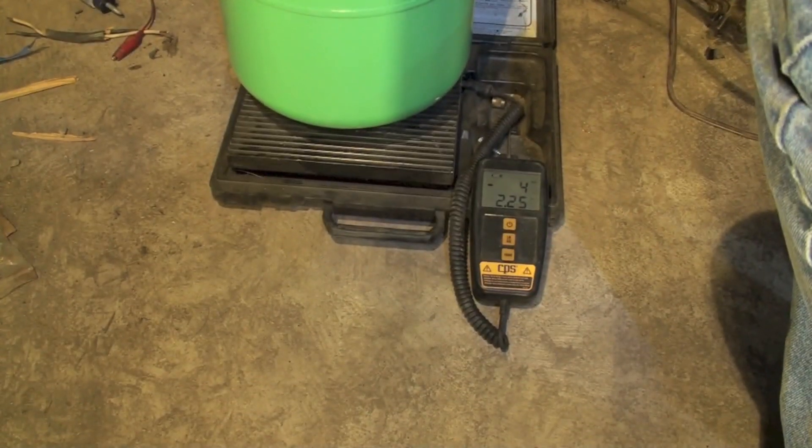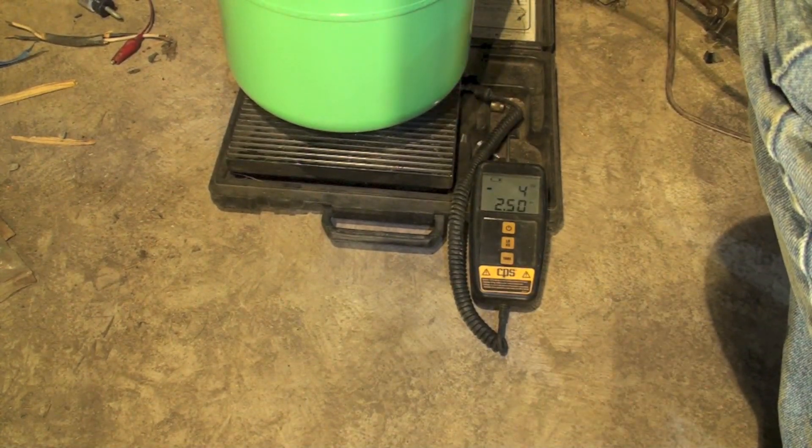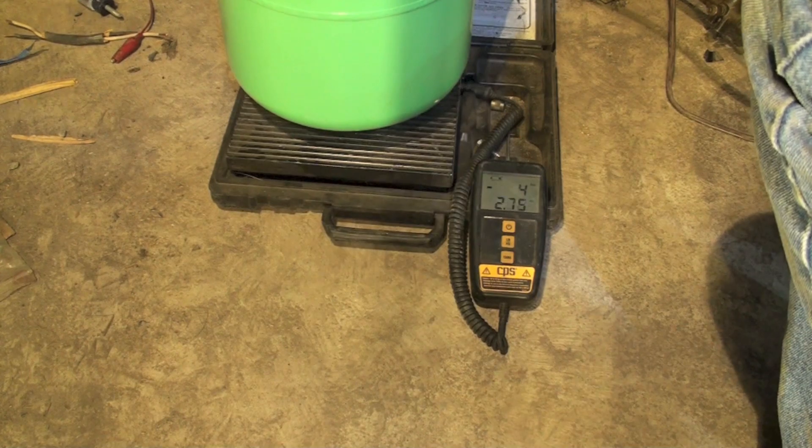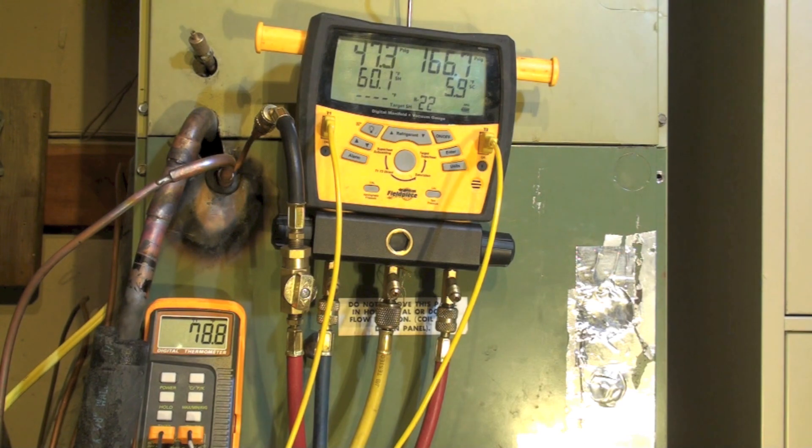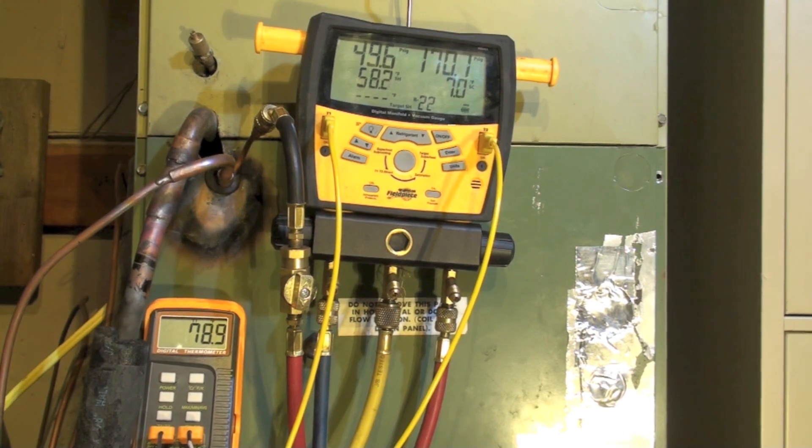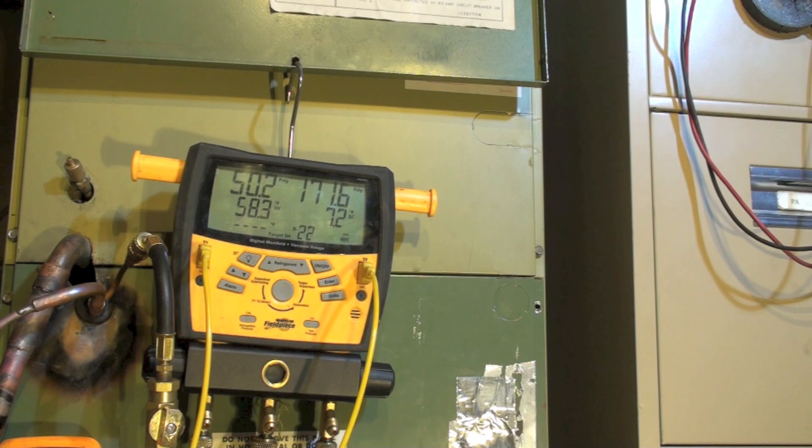I'm going to fire this machine off. Okay, now we have the machine running. We've got a return air temperature of about 79. If we look at the gauge set, we can see we have about 50 pounds low side. Superheat's out of sight, which would be normal.